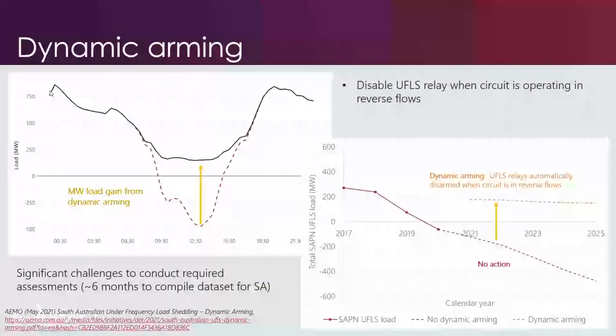This shows the load on a very low demand day as it would be on the UFLS without dynamic arming, and what we can achieve if we implement dynamic arming to push that back up. It gets us to somewhere between 100 and 200 megawatts of load in those very low demand periods, where it should be up around 10 times that, a gigawatt, but it's a heck of a lot better than having it down at negative 500 megawatts. That benefit becomes greater as more PV comes in. It stabilizes the UFLS at around that 100 to 200 megawatt level, rather than having it continue to decline into very negative territory. So an extremely important intervention to have that reverse flow blocking put in place.